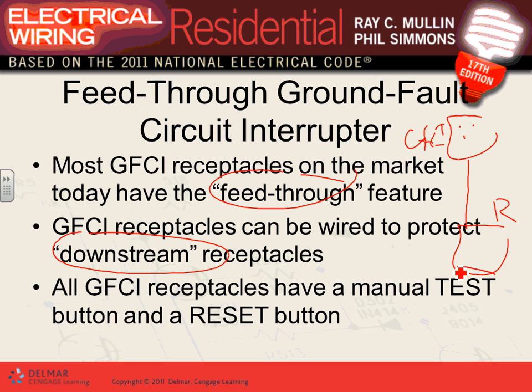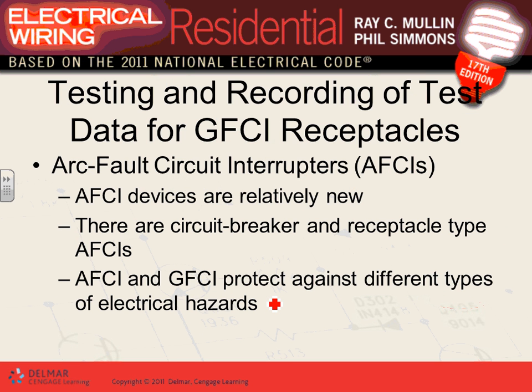GFCIs have to be tested, guys, and there is a reset button. Monthly tested, how many of you guys do that? Monthly test your GFCI to make sure that the mechanism works, and there is a reset button. I do that in my bathroom because I'm shaving all the time. Whenever I'm sitting there, I just push the button. It doesn't take much because it's in close proximity to me. Okay, so that's your GFCI. Any comments, guys, about GFCI? It protects you from shock hazard and is meant to protect the public. We know where the locations are. You can either have a GFCI receptacle, or a GFCI receptacle protecting multiple non-GFCI receptacles, or you can have GFCI circuit breakers. We'll look at a couple of pictures.